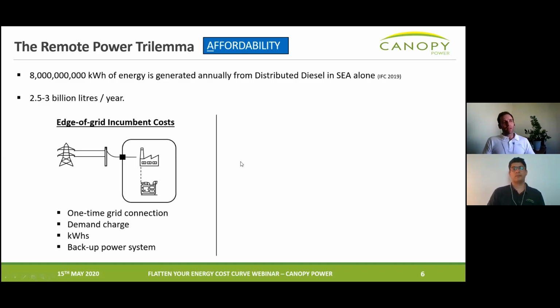Let's look at the two applications where this happens. Firstly, the edge of grids, where you're connected to a grid, but it's not reliable enough for business critical operations, so you need a long duration backup, typically a diesel generator, with a large fuel tank to last at least 3-4 days for the worst blackouts.